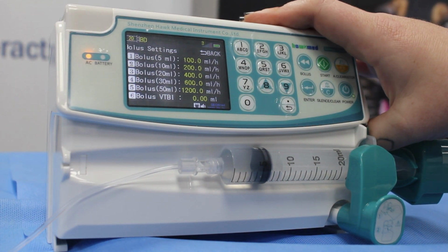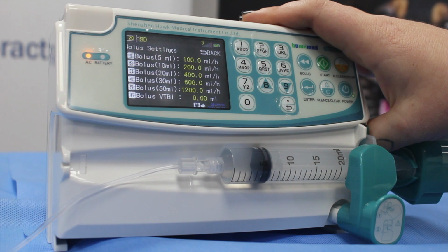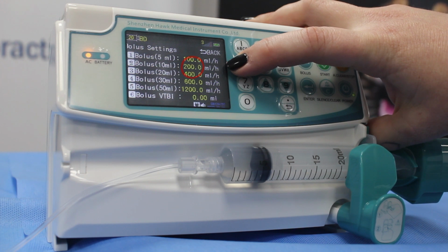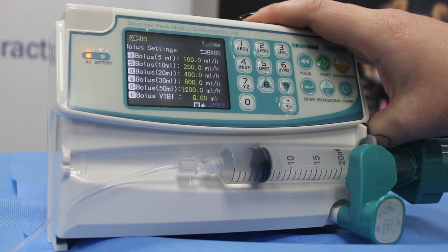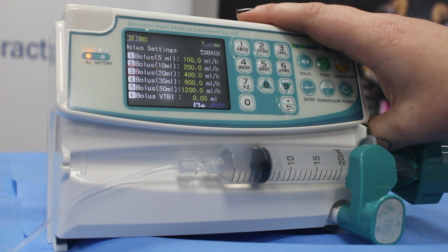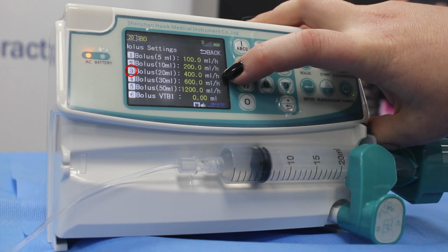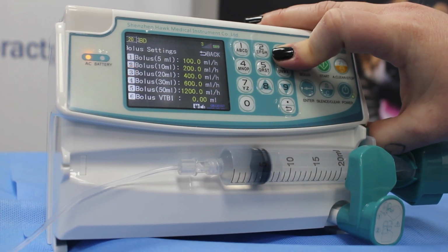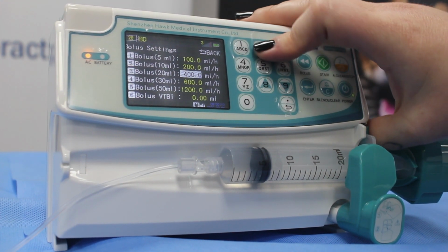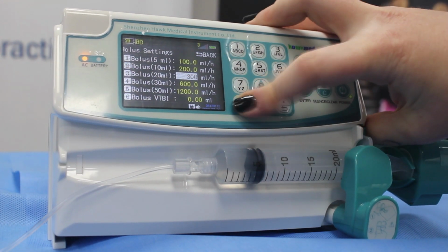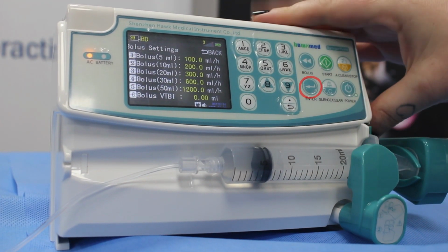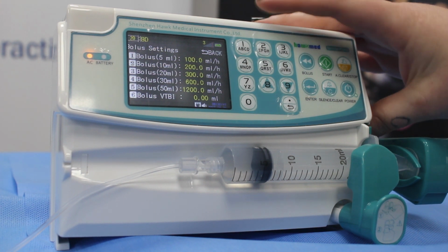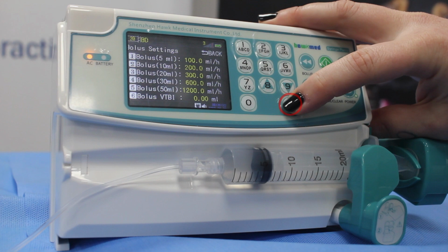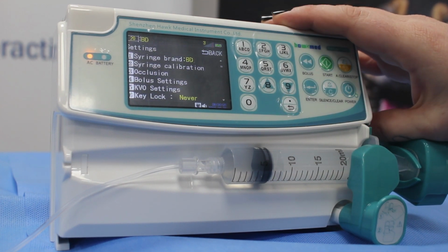Our bolus settings can be customized specifically for each syringe. For example, using a 10 ml syringe would give you a 200 ml per hour bolus rate with these current settings. If we wanted to change that, for example, for the 20 ml, which is currently 400 ml per hour, we could press the corresponding number 3. We could adjust this as required, say we'll pop it down to 300, and press enter again to confirm. We can go back again with the back button to the main menu.